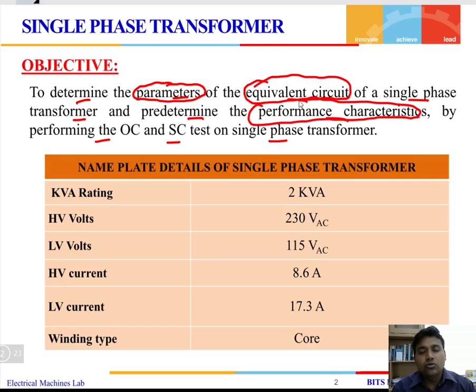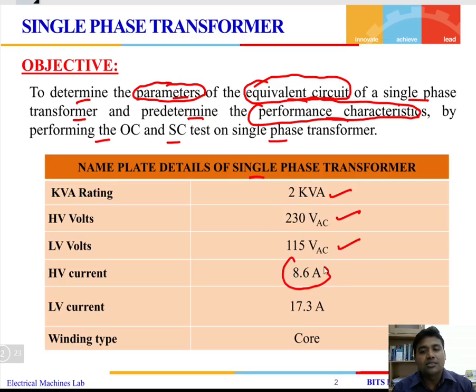These are the two basic objectives of this particular test. We are going to use a single phase transformer whose kVA rating is 2 kVA, high voltage side is 230 volts and low voltage side is 115 volts. The high voltage current is 8.6 ampere, which is the full load current on the high voltage side, and low voltage current is 17.3 ampere. The transformer is of core type.